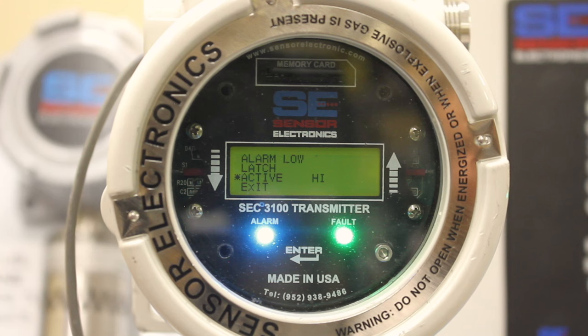active. We have 2 selections here, active high and active low. Active high is probably 90% of the time how the relays are programmed. It's also the default setting. Active high means that the alarm relay will trigger on the rising edge, or as the gas concentration goes up and reaches the alarm set point, it will actually turn the relay on.